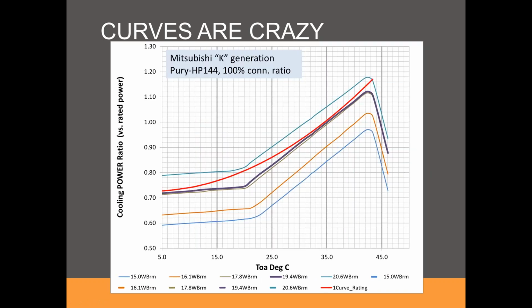However, this now is the cooling power ratio. And you can see that the inflection is a little more pronounced, and a single curve representation misses a fair amount of performance difference between, say, 10 Celsius, which is 50 Fahrenheit, and say 30 Celsius, which is 86 Fahrenheit. So there's a gap here between the purple line and the red line, which in this case shows that if you use a single curve, EnergyPlus will predict higher power than what the equipment actually requires. And by the way, that's a lot of hours during a typical weather year. If you have a moderate climate, this could be 1,000 hours easily, maybe more. So for all of those hours, you would overpredict the amount of power, and you'd underpredict your savings.